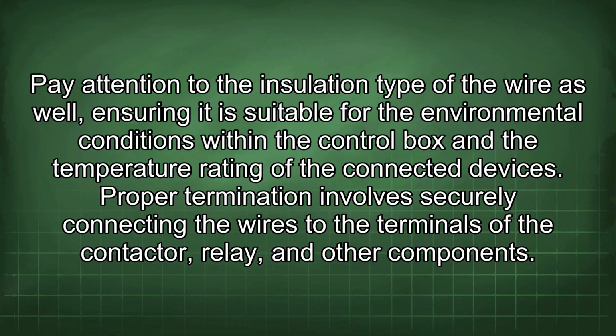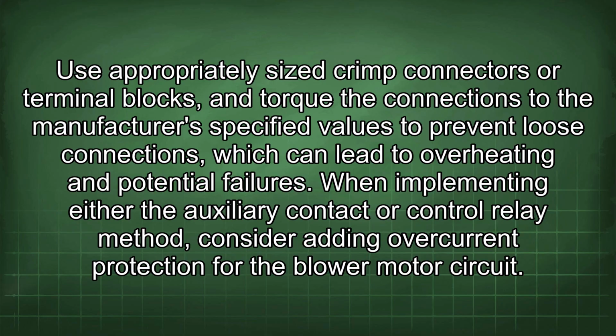Proper termination involves securely connecting the wires to the terminals of the contactor, relay, and other components. Use appropriately sized crimp connectors or terminal blocks, and torque the connections to the manufacturer's specified values to prevent loose connections, which can lead to overheating and potential failures.